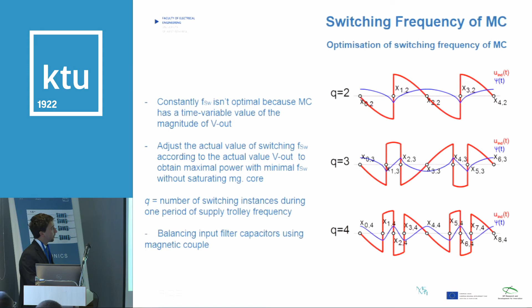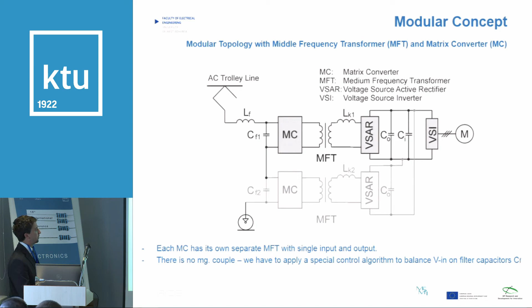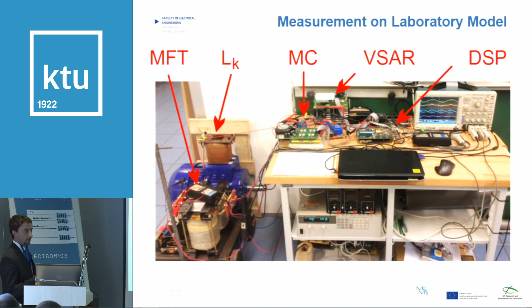There is balancing of input filter capacitors using a magnetic core. On this slide is the separate levels of drives, and each matrix converter has a separate medium frequency transformer. There is no magnetic coupling, and we have applied a special control algorithm for balancing the input filter. On this slide you can see our measurement model: medium frequency transformer, input filter, matrix converter, voltage source active rectifier, and the DSP containing our algorithm.